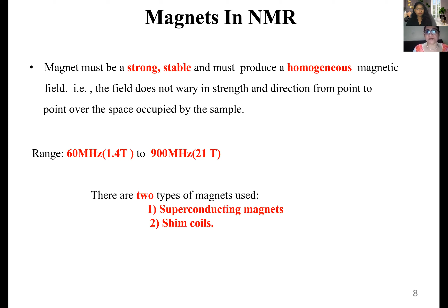Now, there are two types of magnets, as I told you: the superconducting magnet and the shim coil. So let us see what superconducting magnets are. The superconducting magnets are made up of niobium and tin, or niobium and titanium wires. These superconducting magnets are submerged in helium to provide sufficient cooling.